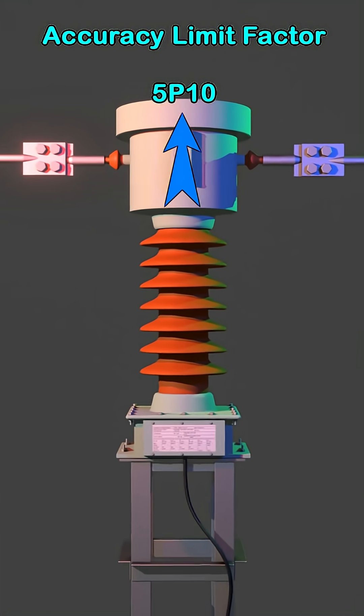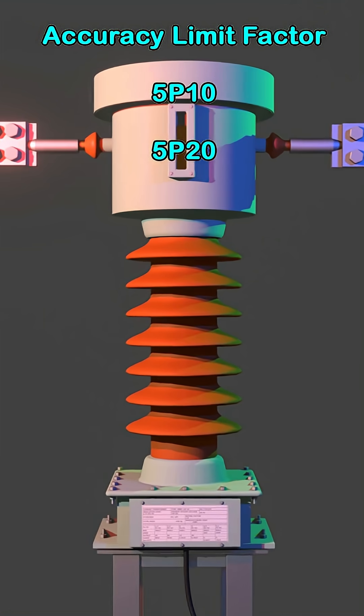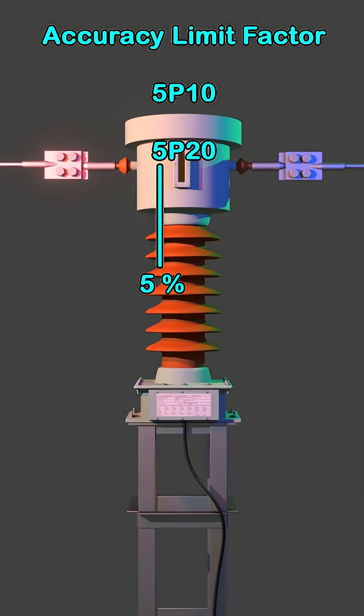The letter P represents protection. Let us take the example of 5P20. It means the protection core of the CT will have a maximum error of 5% within 20 times the rated primary current.